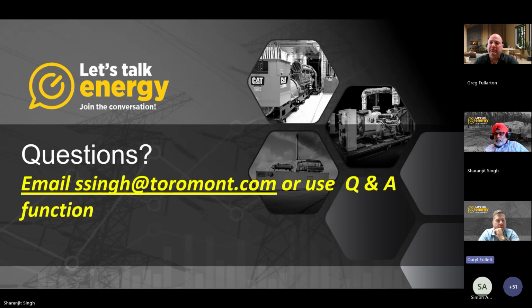Is that something a variance could be applied to, or is it generally pretty strictly enforced? I would suggest strictly enforced. They want to keep the two separate, because a lot of these standby generators have the capability of islanding small mechanical shops and similar facilities, and they don't want generators operating for that purpose. So they want to see records and data showing you've only put this on test for about 1 hour a week or so, just to stay below 60 hours.